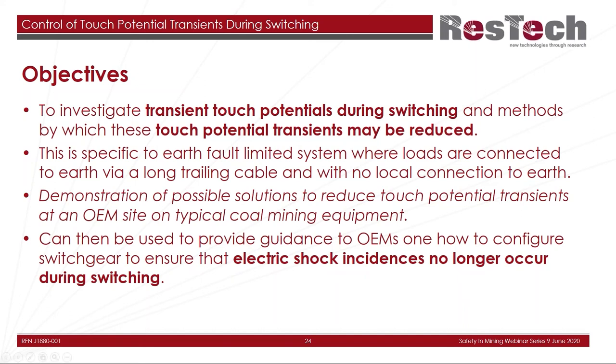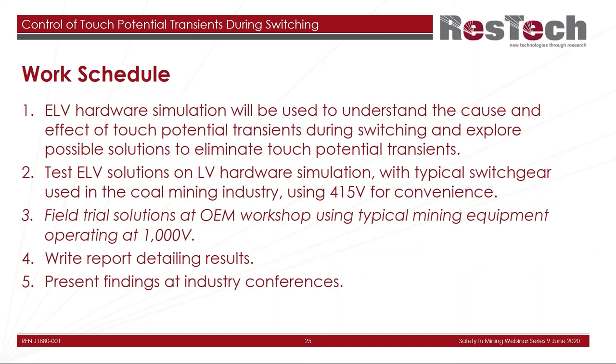The whole idea of the outcome of the research is that we'll provide some guidance for OEMs on how to configure their switchgear, or whether we need to develop some particular device to effectively ensure that electric shock instances no longer occur during switching, so we don't get these events occurring. In fact, it's the secondary effect of these electric shock instances that is most concerning. Whilst they might be perceivable and sometimes painful, they don't seem to be within a range of causing fibrillation. But if you're on a platform at height and you get an electric shock, there's a possibility of falling off the platform and injuring yourself that way.